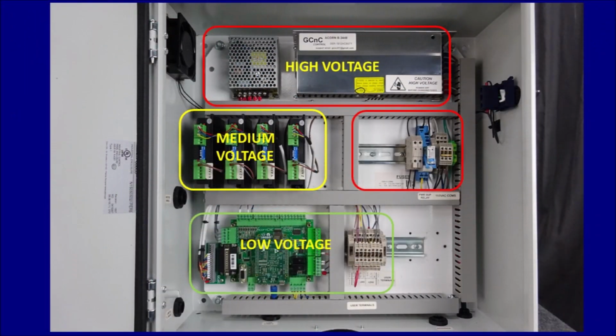This is a real live version of the drawing that you just saw of the interior of that board. You can see that I'm organizing them by high voltage areas, medium and low voltage, trying to keep the low voltage areas as far away from the high voltage as I can. Also keeps my wires shorter, which lowers cost, but more importantly than that, keeps the amount of wire in the ducts down to a minimum, and I try to do everything that I can to eliminate high voltage wire and low voltage signal wires running parallel to each other, and that reduces crosstalk. So in the long run, the more time that you spend planning this, the better that you'll be.